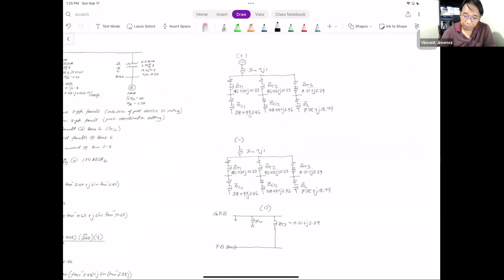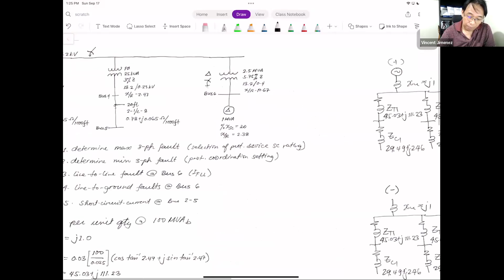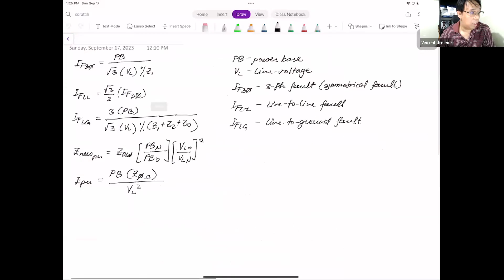So you notice I calculated the positive, negative, and zero sequence. For the IF3 phase, I only need to use the positive sequence, because if you look at the formula I wrote earlier, IF3 phase only calls for positive sequence Z1. For the IF line to line, once you compute the IF3 phase, that's it, just multiply by square root of 3 over 2.